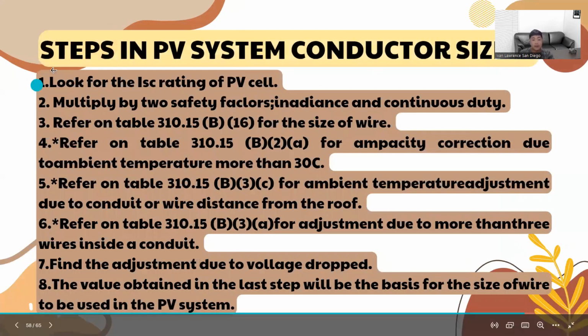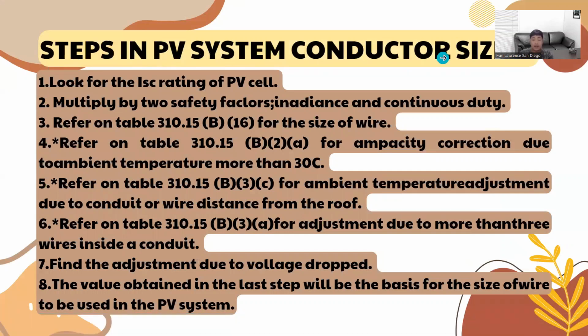Ito naman yung steps sa PV system conductors sizing. First dito is itong look for the ISC rating of PV cell. And the second one is multiply by 2 safety factors, irradiance and continuous duty. Third is refer on table 310.15b16 for the size of wire. Number 4, refer on table 310.15b2a for ampacity correction due to ambient temperature more than 30 degrees Celsius.